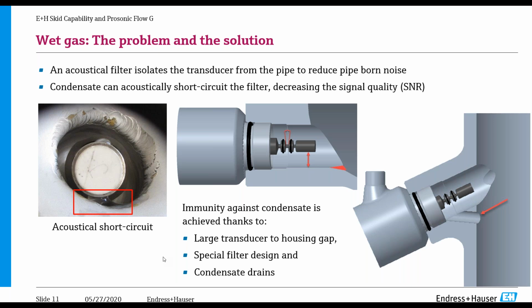So what we've done, if you look in the middle now, this is a cutaway of a meter. We have quite a large gap in between what I call the socket and the transducer, to avoid any type of bridging. Okay, so there we have a large transducer gap. What we've also done is where the socket meets the meter body, we've actually ground out an angle to encourage the condensate to drop out. I'll show you in another picture. In addition, on the right side, if the meter is installed in a vertical installation, we've added a drainage hole.